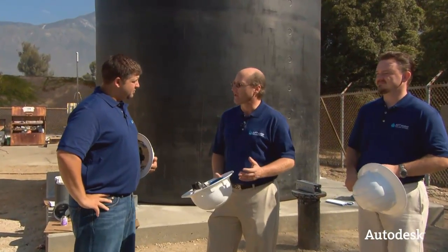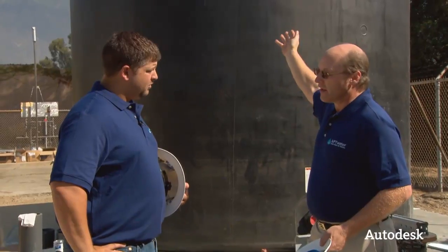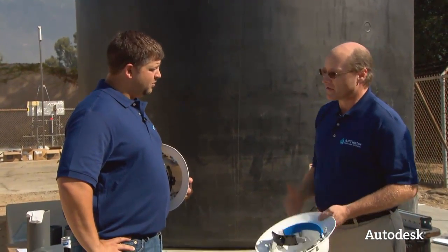So we're using naturally occurring bacteria that are in the ground, and the contaminant is being removed by these naturally occurring bacteria. The overall process starts at the well, of course, that's been contaminated over years of agricultural use. We pump up the water into this large buffer tank, and from that tank we feed our system. Our system consists of 3 basins full of media that have hollow fibers in it that contact the water and treat the nitrate out.